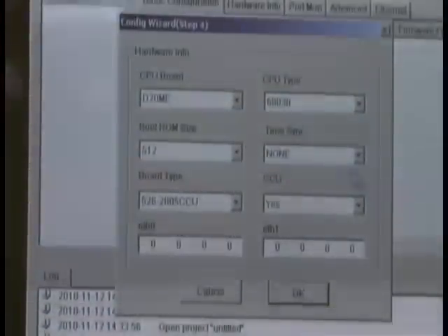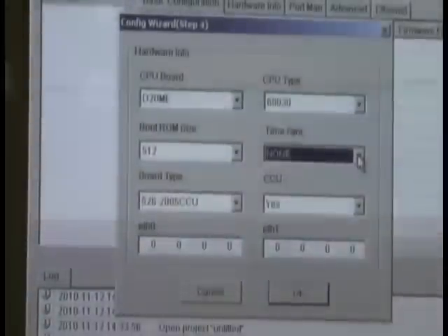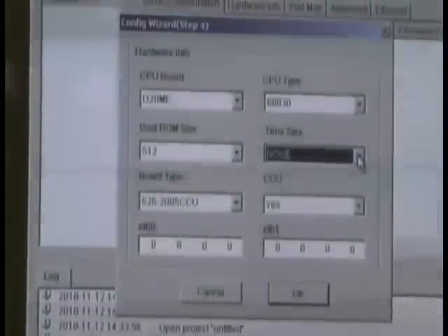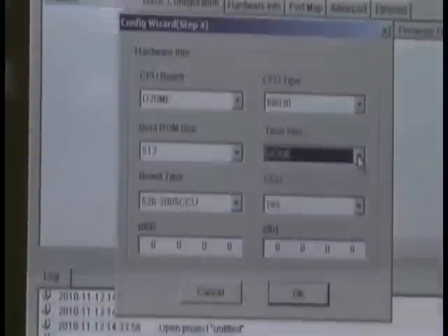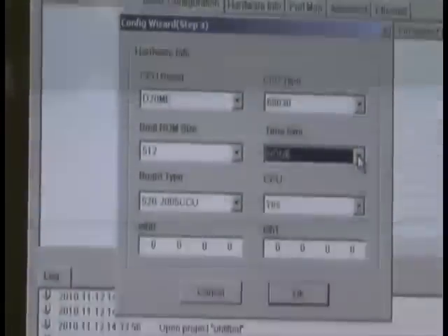Now you just select your D20 board type and whether you want to time sync. This time sync parameter specifies whether or not the D20 emulator or the D400 software controls the time of the unit. And this is just because you may have DNP protocol, or you may have protocols running on the D20 that are sending it time syncs, but you may prefer to have the D400 time syncing to a network clock or to a protocol on that. So this just allows you to select which side has say over or control over the system clock.